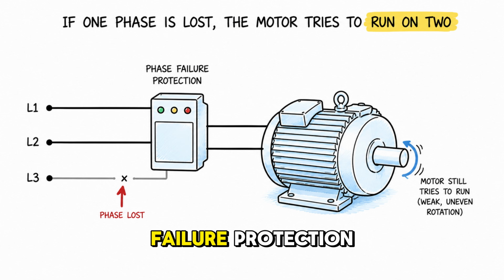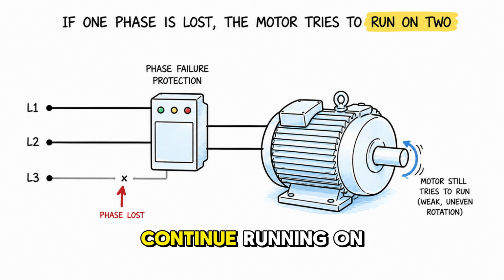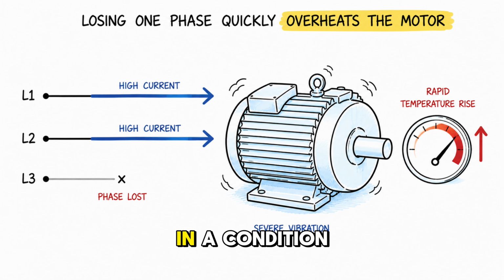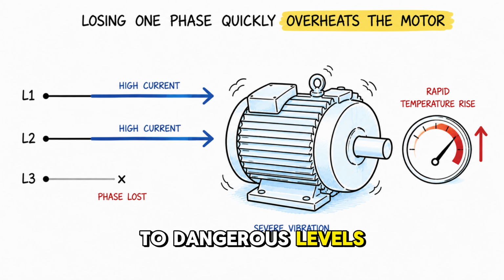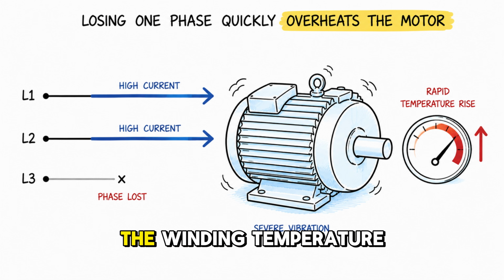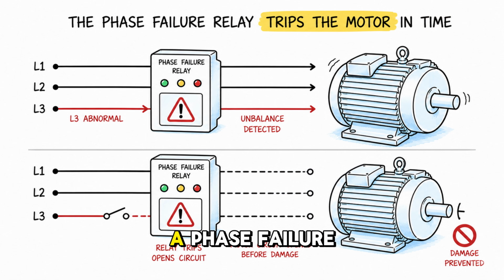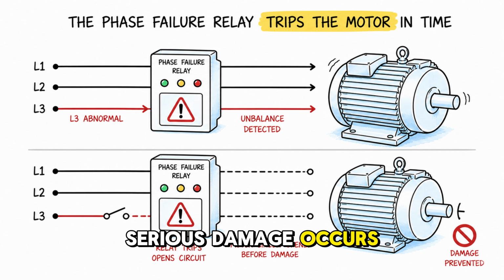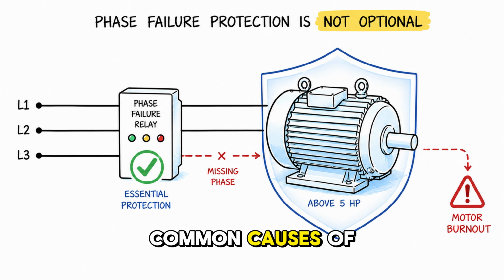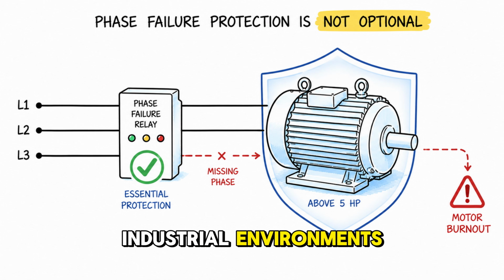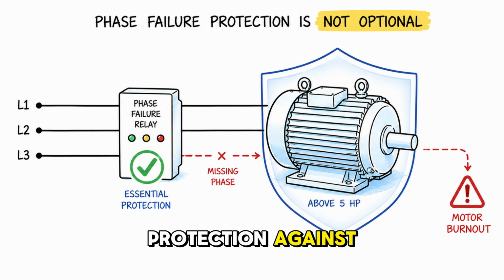The third device is phase failure protection. If one of the three supply phases is lost, the motor attempts to continue running on just two phases. In a condition like this, the current in the remaining two phases rises to dangerous levels. The motor begins to vibrate severely. The winding temperature climbs rapidly. A phase failure relay detects this voltage or current unbalance immediately, and it trips the motor before serious damage occurs. Phase failure is one of the most common causes of motor burnout in industrial environments. Because of this, protection against it is not optional on any motor above 5 horsepower.